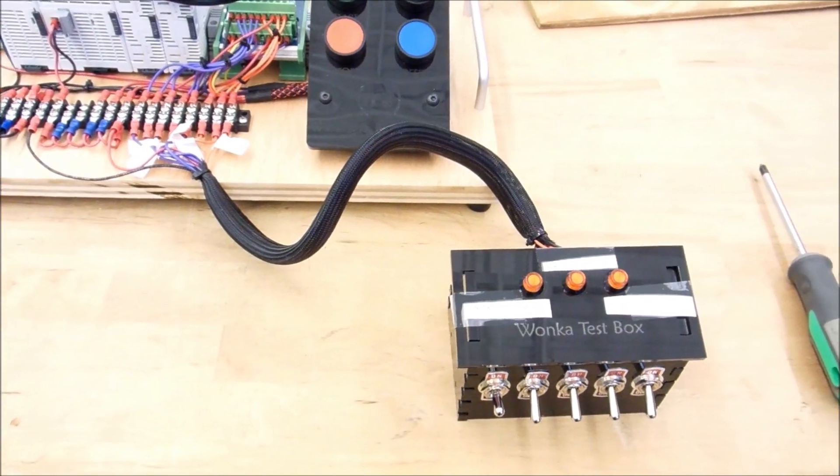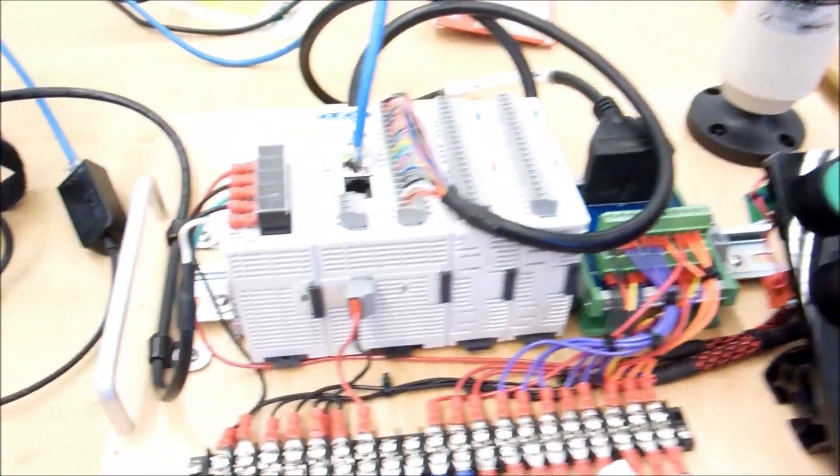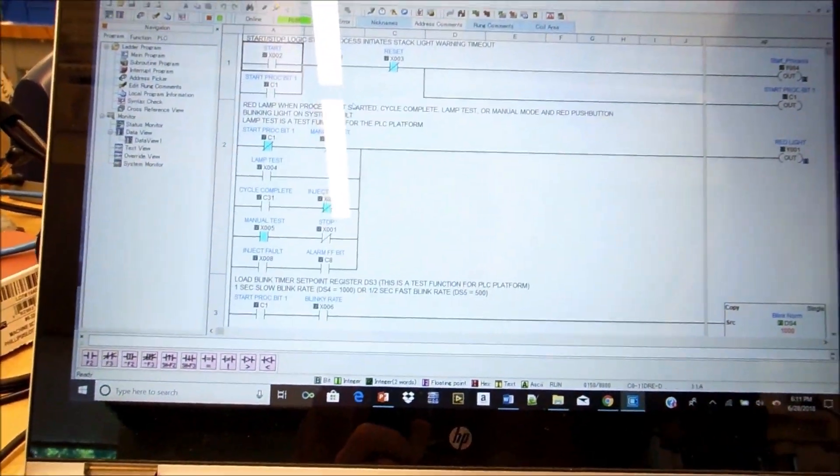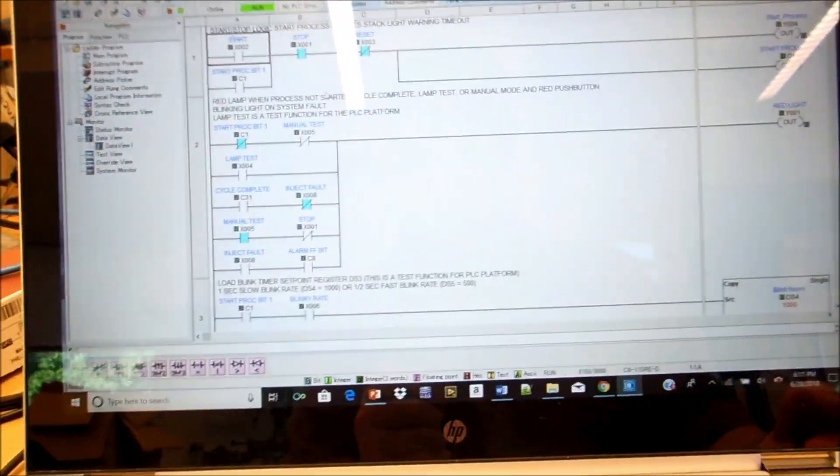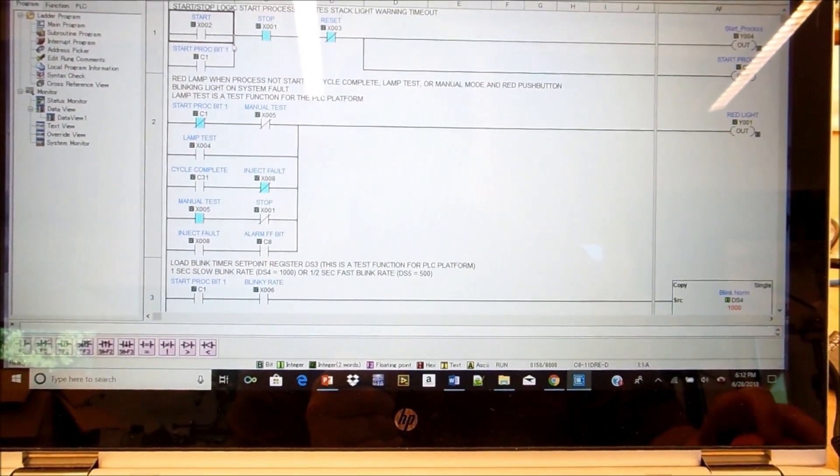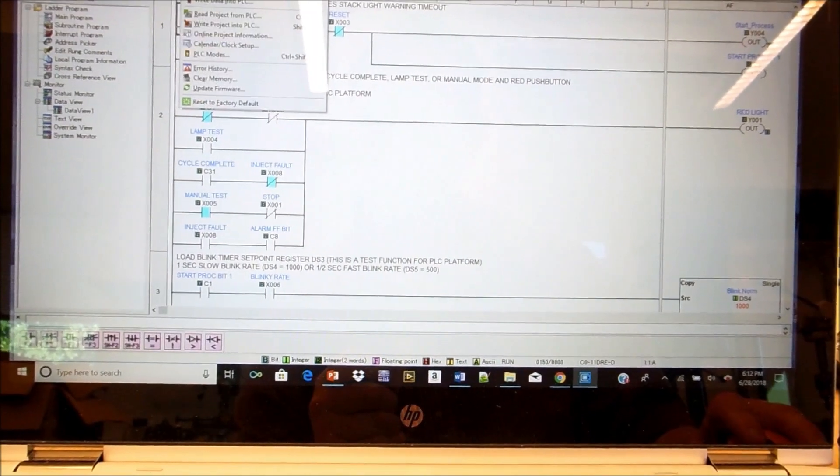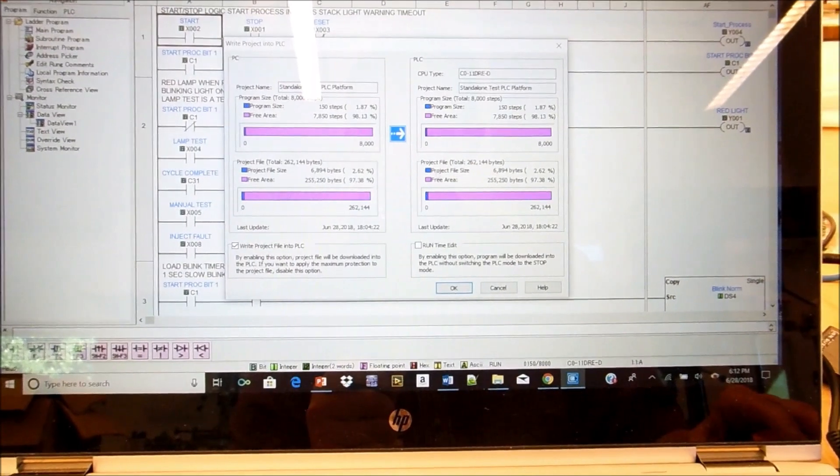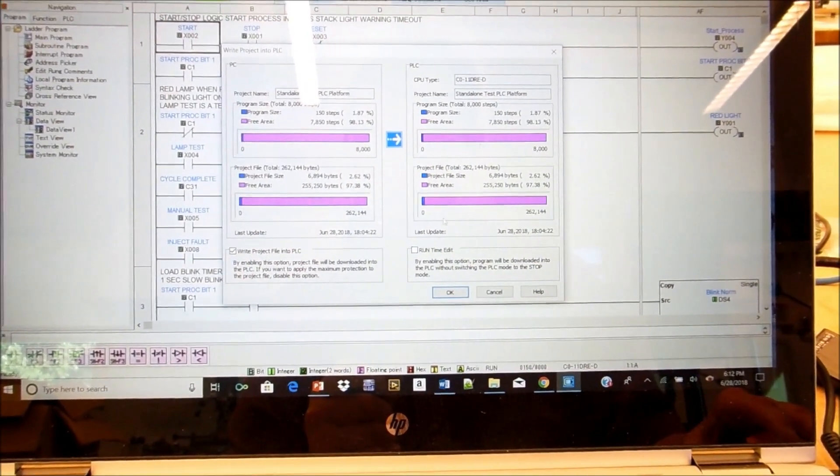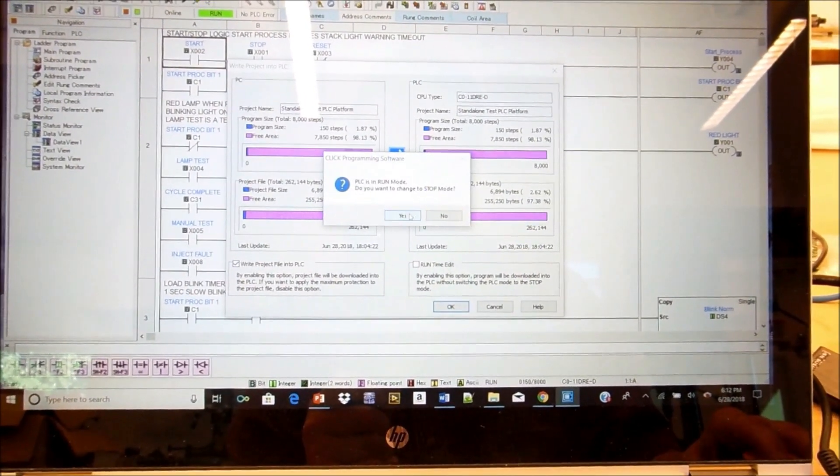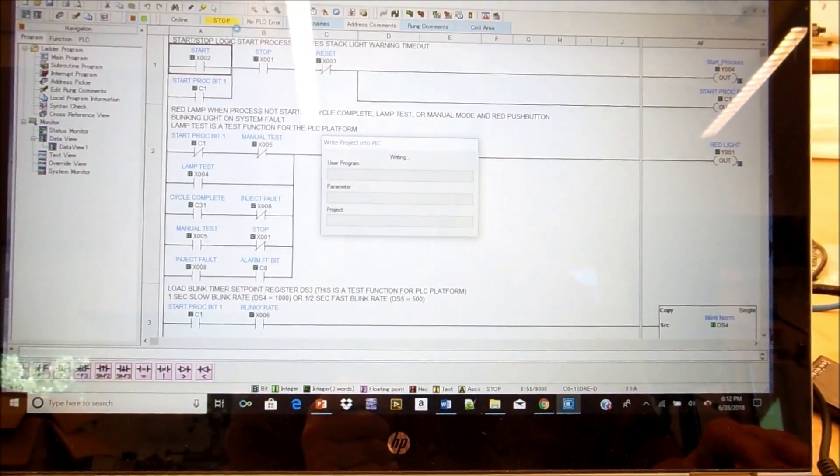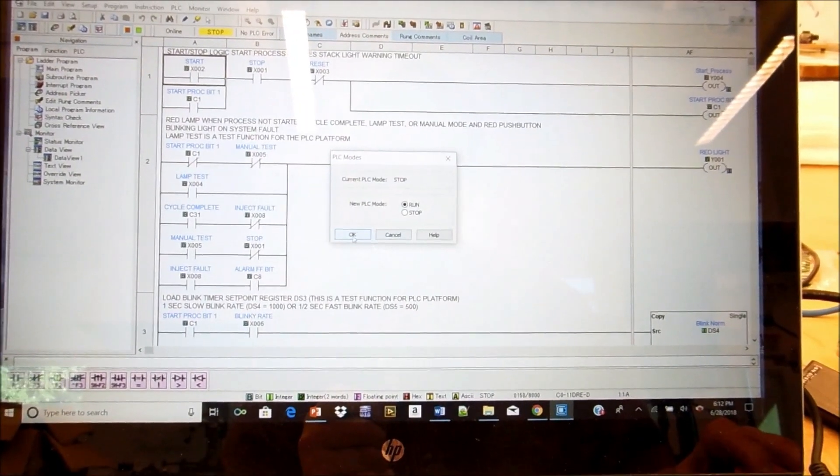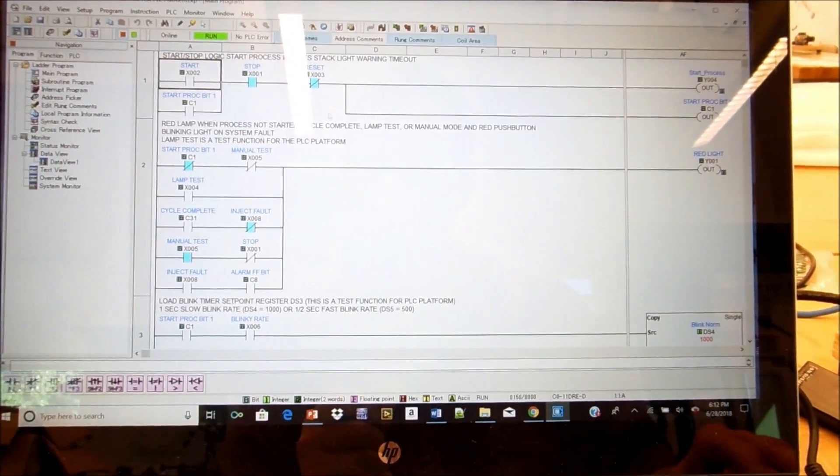Okay, so now we've got the Wonka box hooked up, and what we're going to do is we're going to download the program. Now this is a standalone, and you can't see it very well because of my glossy screen, but we've got a program running, and this is a standalone program. And if we're going to download it, we can just write the project into the PLC. It comes up with some screens about what you're trying to load and what you're trying to put it into, and all you do is just click on it, change from run to stop. You can see we're in stop mode while it loads, and when it's done, it'll say go back to run mode. Yep, and now we're in run mode. We can monitor this.